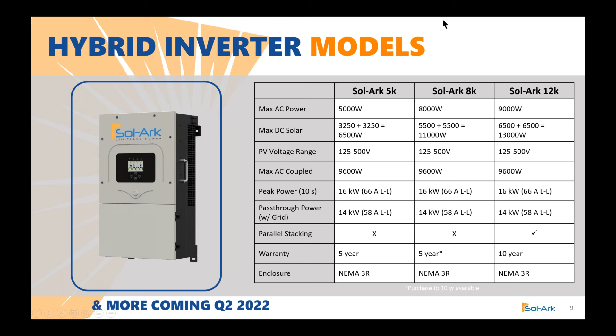Pretty please. Okay, touching on the main difference between the three units, starting with parallel stacking: both our 5K and 8K inverters are standalone units, they cannot be stacked. Our only stackable unit is the Sol-Ark 12K, and soon to be the 15K as well. The Sol-Ark 12K can stack 8 in parallel in a 120/240 configuration, or up to 9 units if you use 208 3-phase.